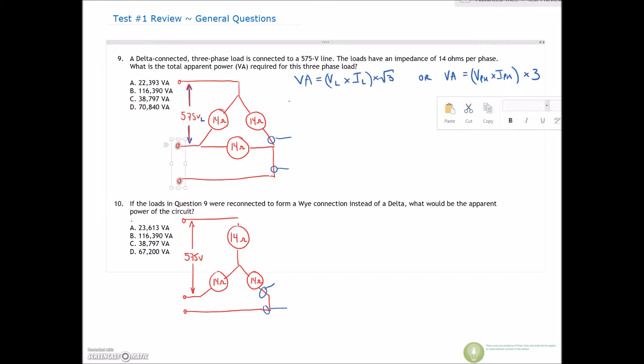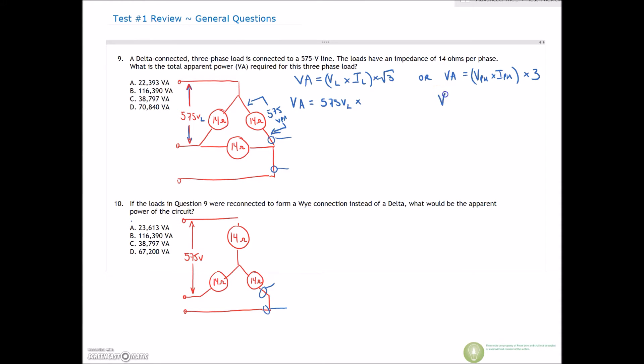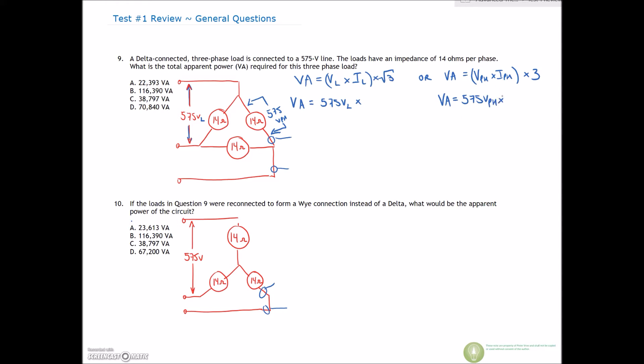We know the line voltage of 575 volts, but we don't know our line current yet. For phase voltage — well, we know that, because for a delta connection the voltage on the phase is identical to the line voltage. So our VA here uses 575 volts on the phase.